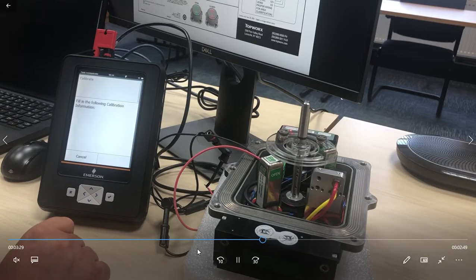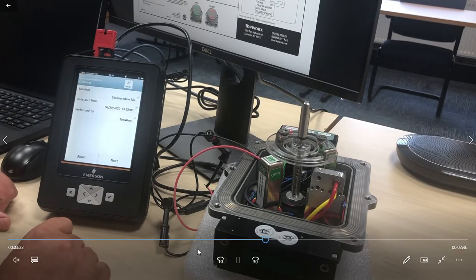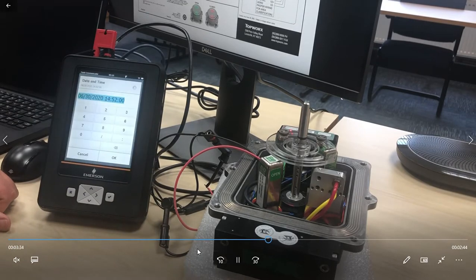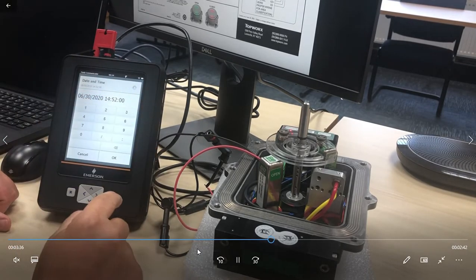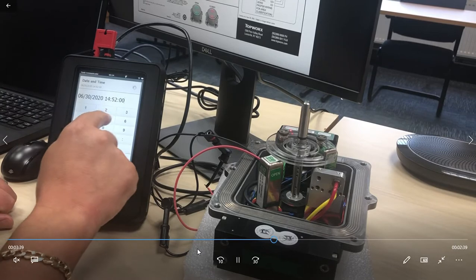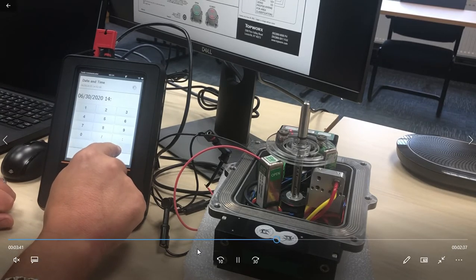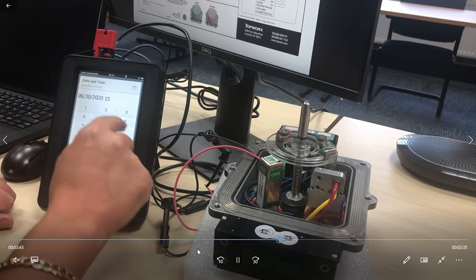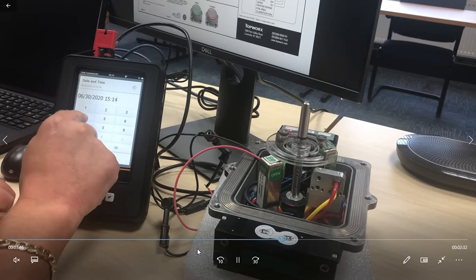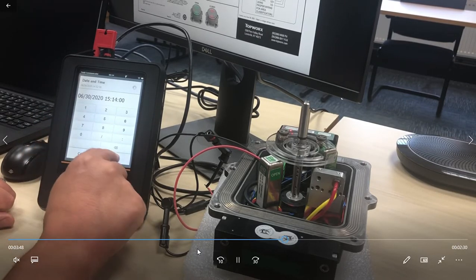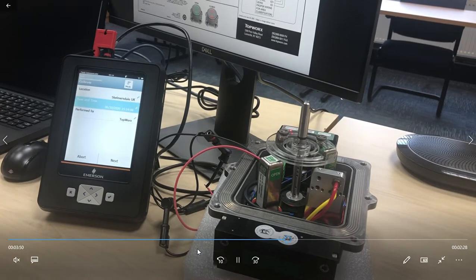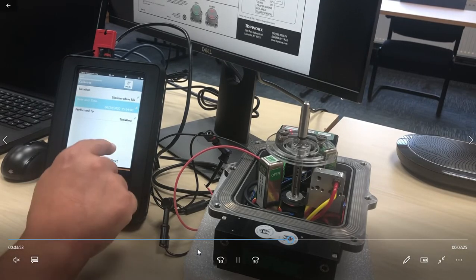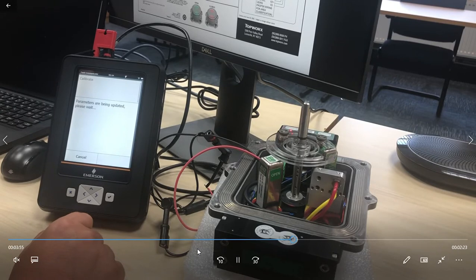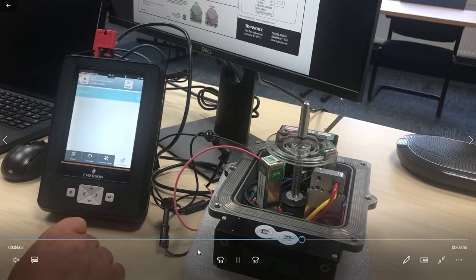And now we're being asked to fill in the calibration information, and again this is stored on the device. So in this case we're just changing the date, but you can put a signature on there, a date, you can put any information that you need, and obviously this satisfies some of the requirements that you may have within your quality procedures, and also on site there may be other procedures that you need to satisfy. So the parameters are all set now. And parameters are updated, so it's giving you an indication that the method is complete.